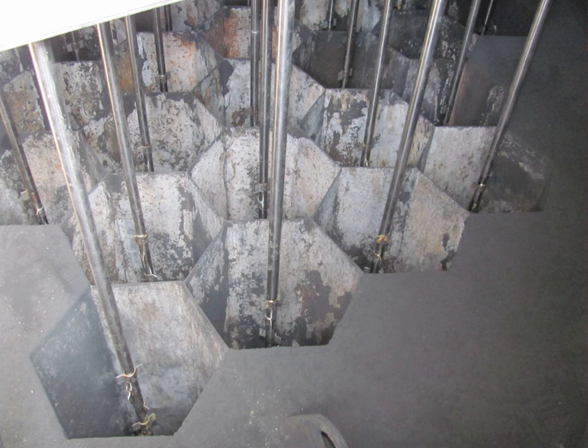If these conductive particles are coarse, they can be removed upstream of the precipitator by using a device such as a cyclone mechanical collector. The addition of liquid ammonia NH3 into the gas stream as a conditioning agent has found wide use in recent years. It is theorized that ammonia reacts with H2SO4 contained in the flue gas to form an ammonium sulfate compound that increases the cohesivity of the dust. This additional cohesivity makes up for the loss of electrical attraction forces. The table below summarizes the characteristics associated with low, normal, and high resistivity dusts.